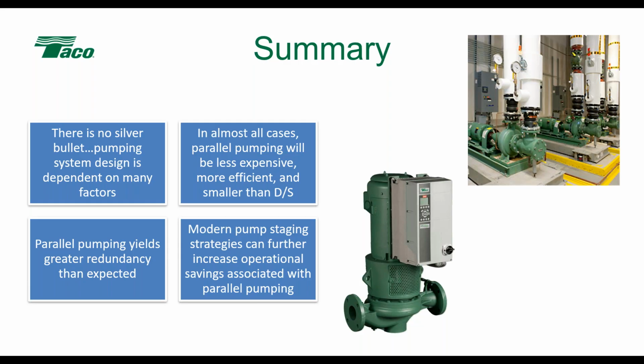Hopefully, one thing you've taken away from this today is that parallel pumping yields greater redundancy. And hopefully you understand better what happens when we have pumps in parallel and where they're actually going to operate if one pump out of the parallel set fails. Couple all this with the staging strategies that we have developed, which can further increase your operational savings associated with parallel pumping, and get away from straight speed-based staging and allow us to do efficiency-based staging with all that technology that's built into the VFDs.